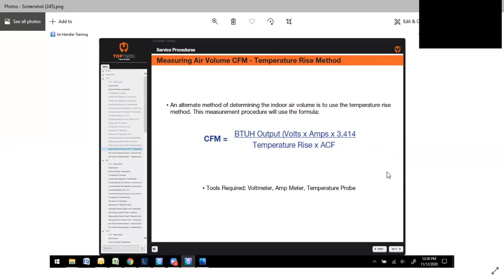This is kind of an important formula to remember. You can use different flow hoods to calculate your airflow, but a simple way to check your airflow, especially out of an air handler, which we're talking about, is this simple procedure right here. It will give you your CFM. It's your BTU output, volts times amps times 3.414, divided by temperature rise and your constant.